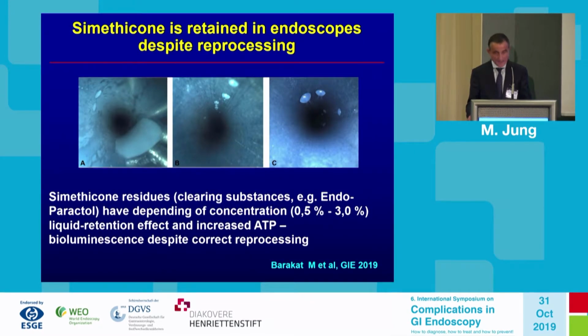So simeticone comes into question. Simeticone is a clearing substance we often use to destroy the bubbles in the stomach or in the colon. But simeticone has, depending on concentration, a liquid retention effect. And this was proven by an increased ATP bioluminescence test, despite correct reprocessing. So simeticone is no longer recommended by the manufacturers, because by adherence to liquid in the small channels, this can give rise to biofilms.